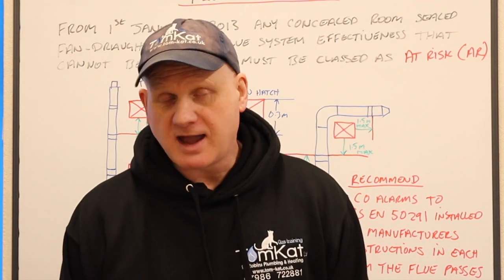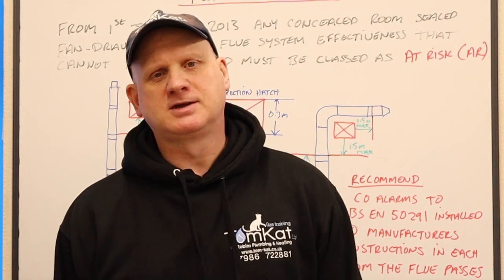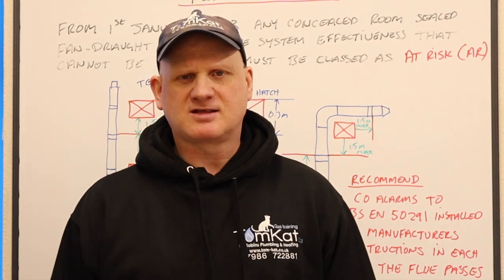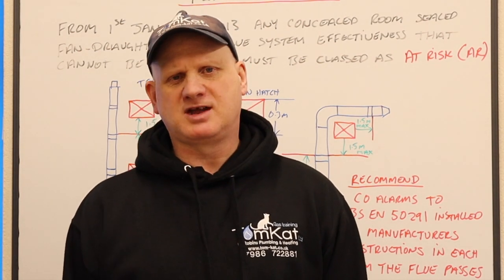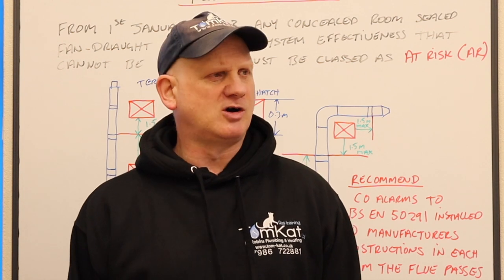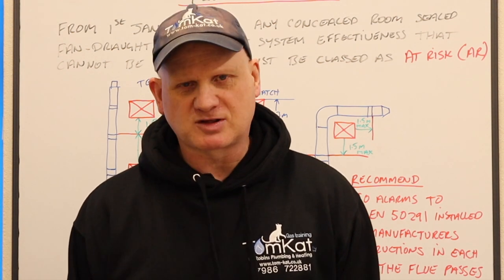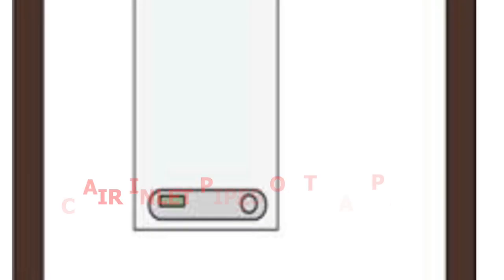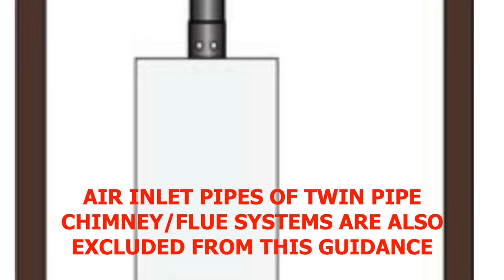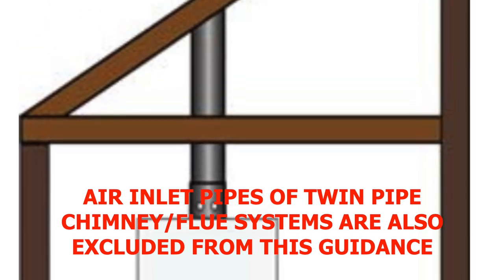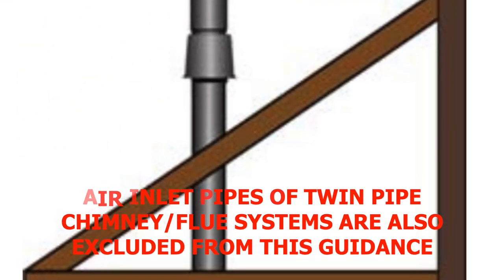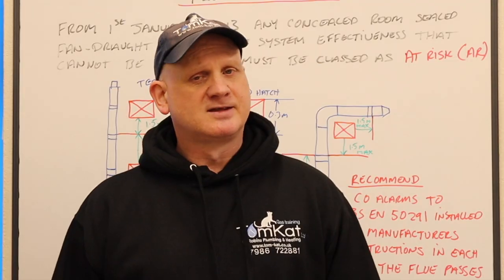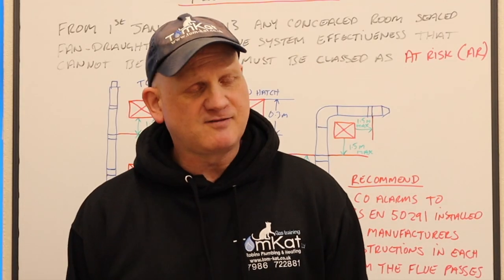What do we mean by a flue in a void? Basically, it's a flue system that's been boxed in from a room-sealed fan-assisted appliance. That doesn't mean back boilers or condensing boilers with a specialist flue system put down a chimney, or a flue system on a flat roof where it's a vertical flue going through the roof and you can see the joints. That's not what's considered a flue in a void.